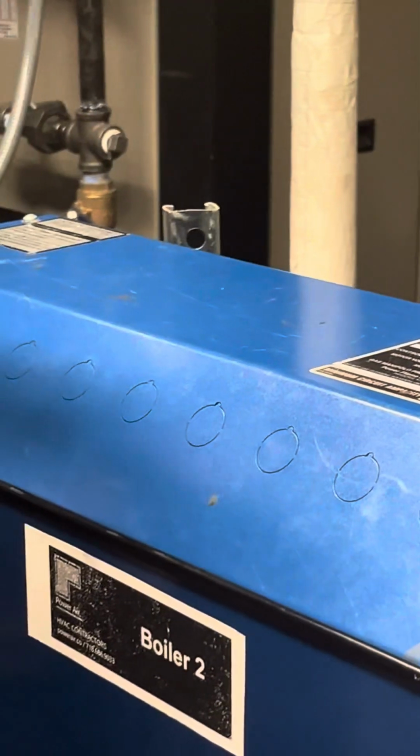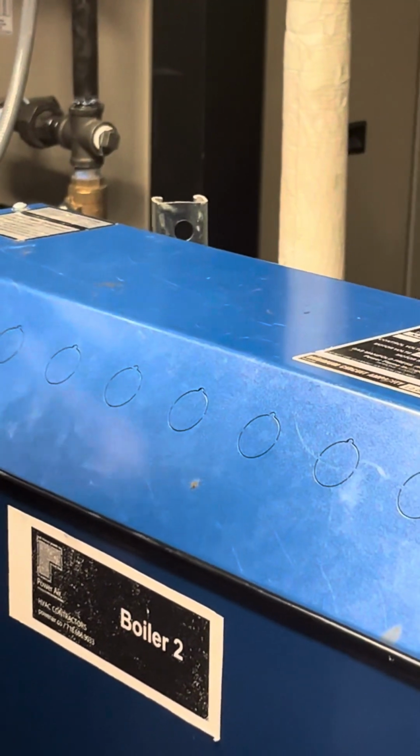Basic error codes. Okay. The most common ones you're going to come across is for your pilot, which is going to be a 2-1. Code 2, diagnostic 1. You're going to come across 3-0, it's going to be air switch, and it's all in there. I'll mark out the ones that are pretty much the most common ones that you guys are going to see. That's going to help you. If you're going to diagnose yourself or have a service company, you can tell them what's going on, or if you want to try to diagnose it yourself, which I wouldn't recommend. But that's the way, it's not going to give you any other information other than a code.